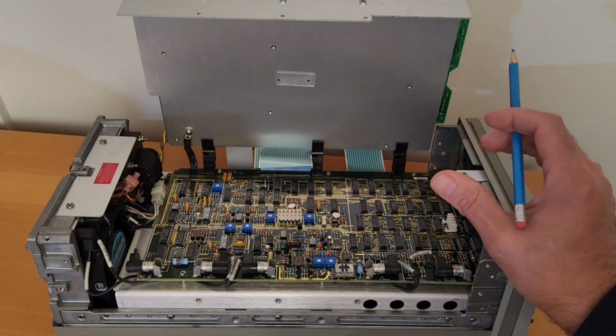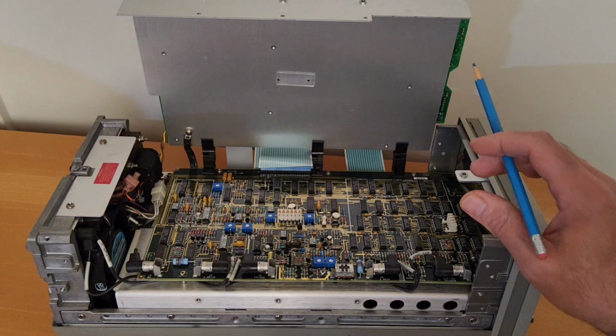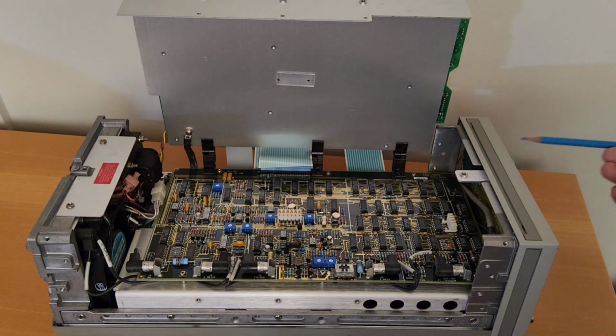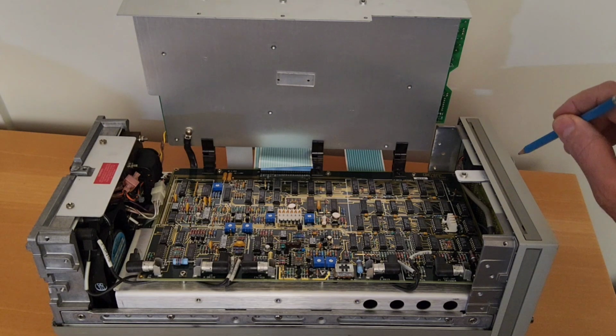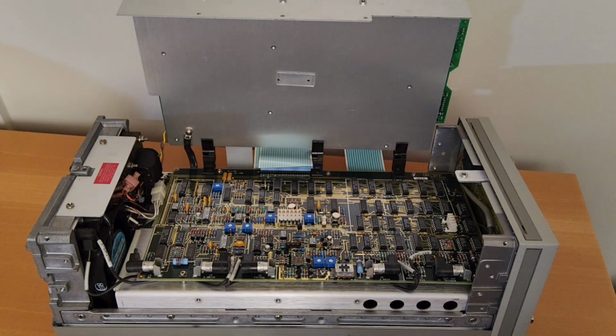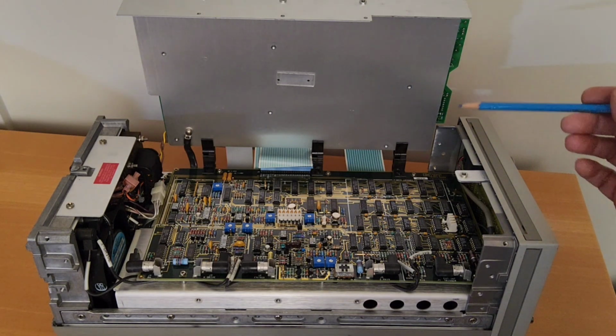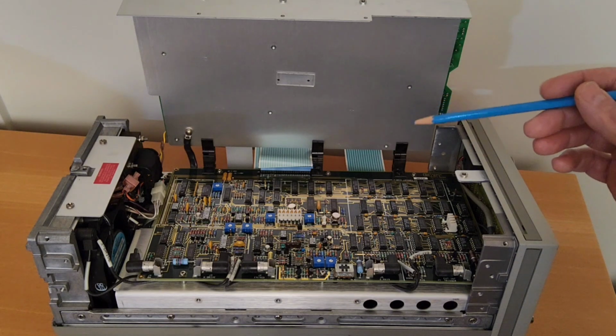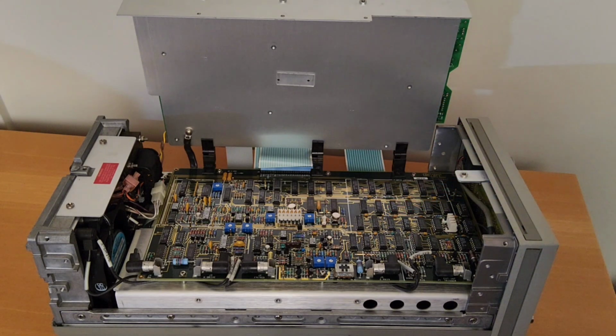kind of like adjusting the knob, so to speak, to ensure that the signal that's being produced on the output meets the user expectation by around 99.9% or better. So, although the signal is generated in analog form, there is precision calibration of the signal's amplitude, shape, symmetry, and frequency that's achieved and controlled by the microprocessor board, and all that controlling is done mainly via this interface board here that controls all modes of operations like phase lock, sweep, gate, arbitrary modes, etc. And that's why this board is called the mode board.